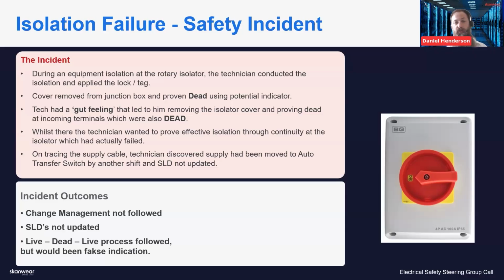So he removed the cover from the isolator to prove dead at the incoming terminals. As he's proven dead there, doing the live dead live process, he's discovered that they were also dead. So he thought, what's gone on here?